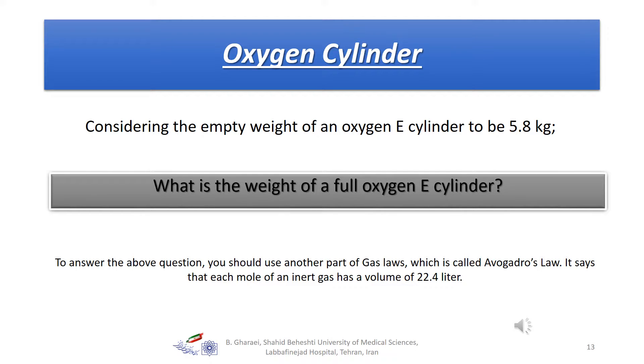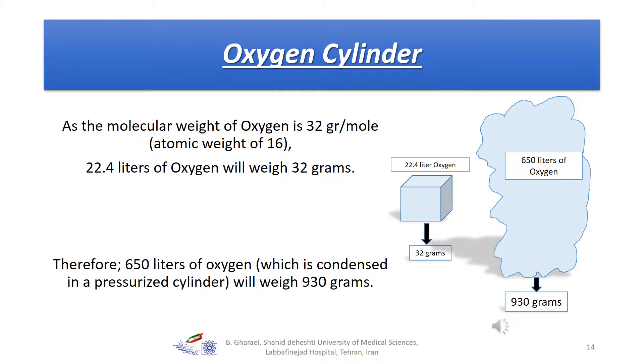Now, I would like you to solve this from a different method. Considering the empty weight of an oxygen E cylinder is 5.8 kilograms, what is the weight of a full oxygen E cylinder? To answer this, you should know Avogadro's law: each mole of an inert gas has a volume of 22.4 liters. Since the molecular weight of oxygen is 32 grams per mole, each 32 grams of oxygen has a volume of 22.4 liters. When you have 650 liters of oxygen, it weighs approximately 930 grams.